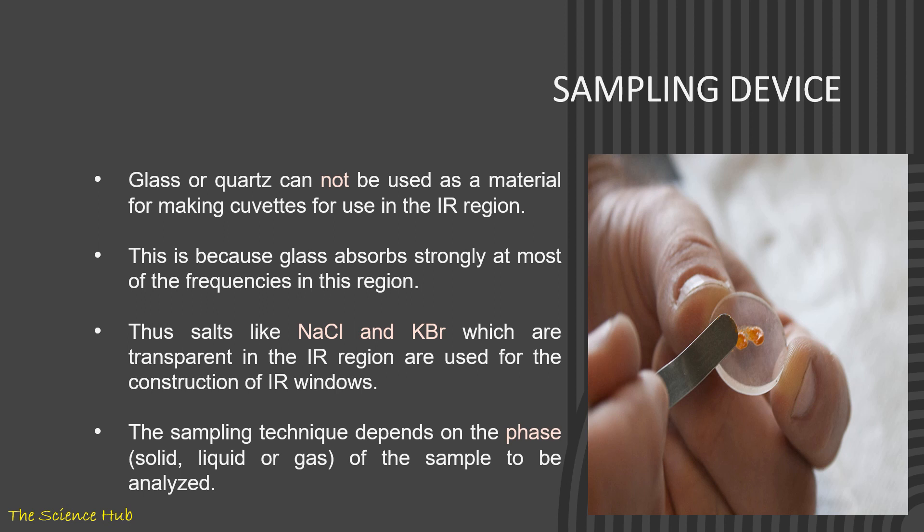Sampling device: glass or quartz cannot be used as a material for making cells for use in IR region. This is because glass absorbs strongly at most of the frequencies in this region. Those salts like NaCl and KBr which are transparent in the IR region are used for the construction of IR windows. The sampling technique depends on the phase—solid, liquid, or gas—of the sample to be analyzed.